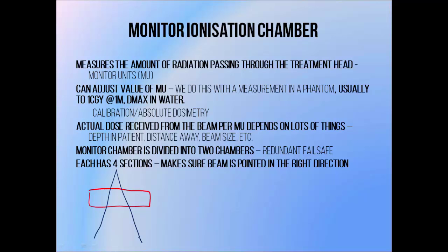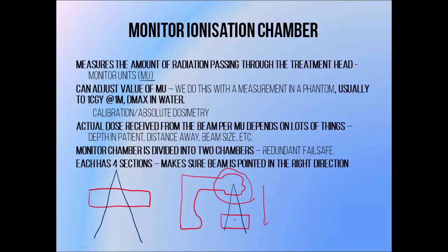The monitor chamber measures radiation in monitor units, or MU for short. When setting up a patient treatment, we might program a machine to deliver 100 monitor units. The monitor unit tells us how much radiation is coming out of the treatment head, but the amount of dose absorbed from this beam by a target depends upon a lot of things outside of the treatment head — for example, how far away it is from the radiation source since radiation drops off with distance, how deep inside the patient it is, and even the size of the beam used.